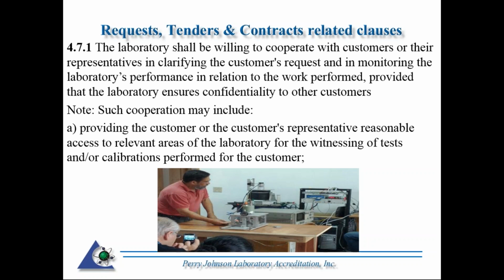So this is basically stating, and particularly with the note, if your customer wants to basically come on your facility and watch what you folks do best, performing the testing under your scope or calibration, you should provide them that cooperation, provided that you ensure the confidentiality of other customers.